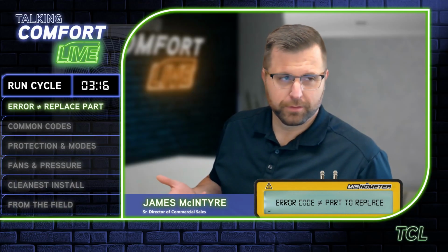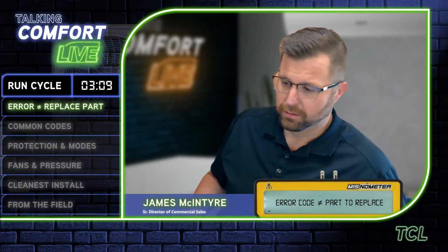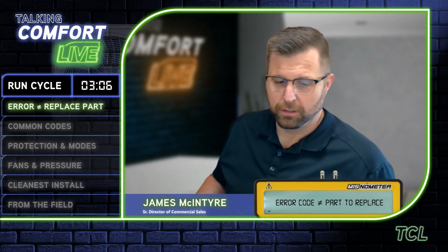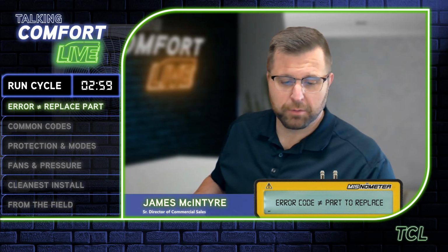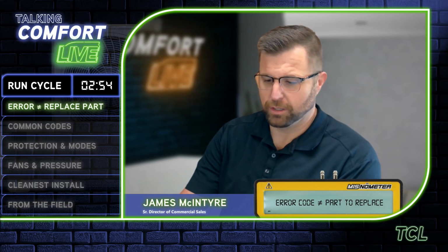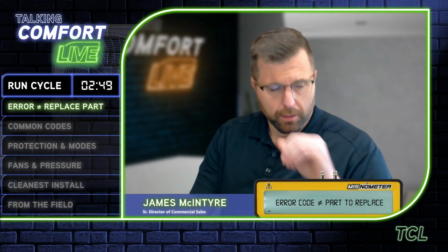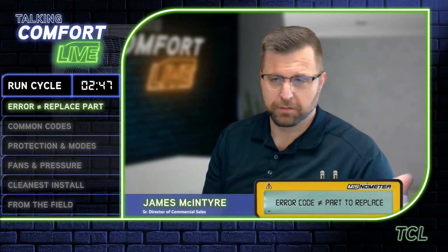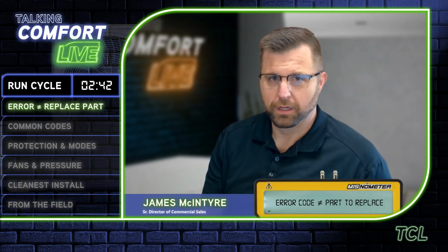Yeah, I like the street address thing. Absolutely. Sometimes the error code is telling you maybe I've got low superheat or I'm returning liquid, flooding my compressor. So what does that tell me? I might hook up gauges and go find out basically the same thing, but the unit just tells you that itself. So it gives us a place to go. Now, where you go find that information can depend on what you're looking for.